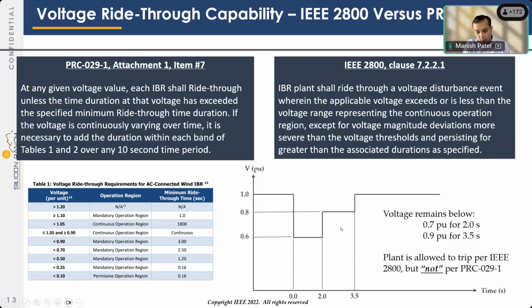So if you have a hypothetical event like this, voltage drops from nominal to 60% at zero time, back to 80% at 2 seconds, and back to nominal at 3.5 seconds. The plant is allowed to trip for IEEE 2800, but not for PRC-029, right? So again, I don't think I want to say what is right or wrong. I don't want to get into a debate where we discuss the interpretation of this English language, right?